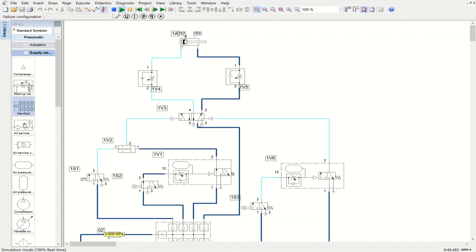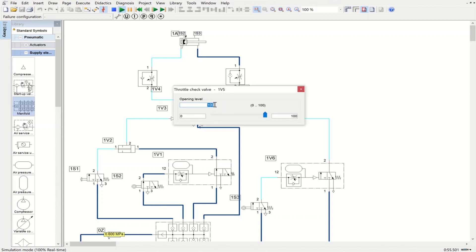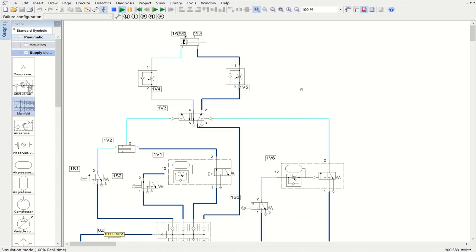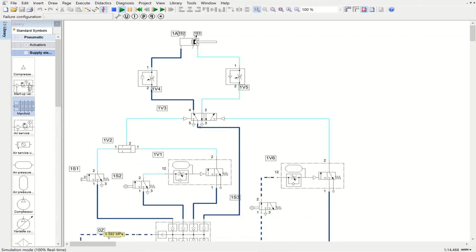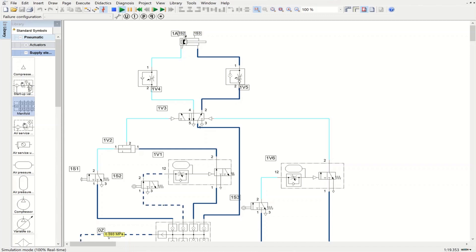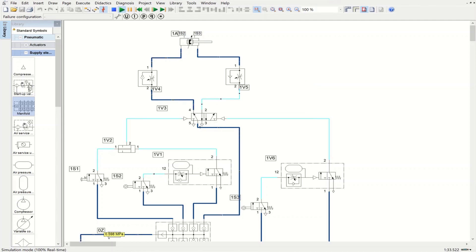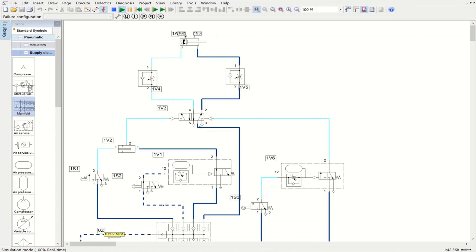The problem states we need control over the speed of the piston — one side should have slower motion. To do that, I change the opening level of this throttle check valve to 10 and observe how it affects the system behavior. With that change, we have a noticeably slower advancing motion. If I change the opening level further to 1 and restart the simulation, we get a very slow motion towards the fully advanced position, followed by a time delay, while the retraction remains fast since we didn't change that side's opening level.